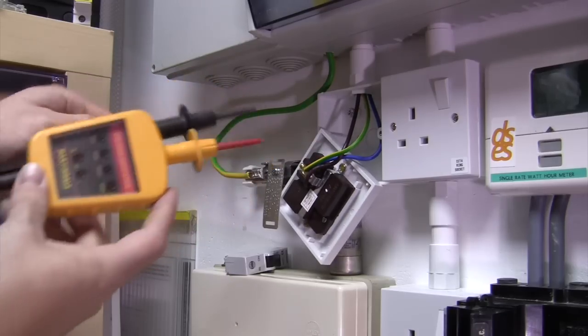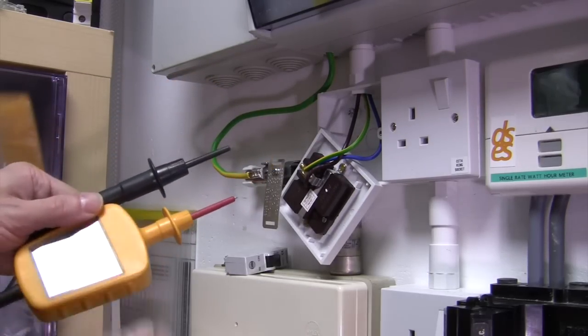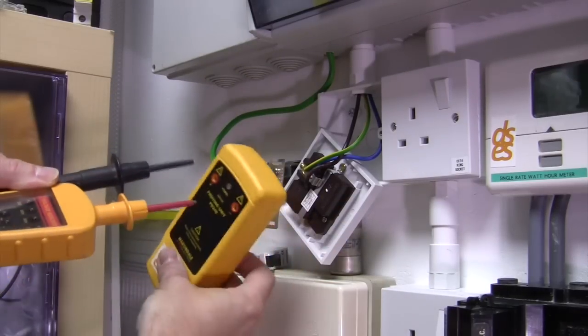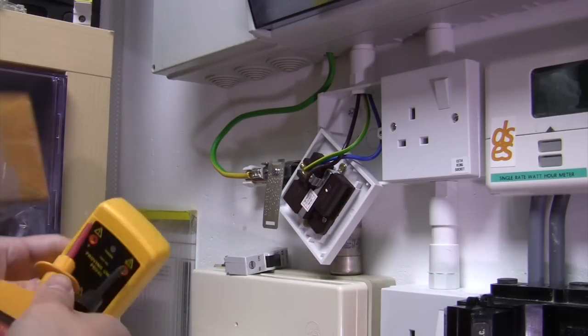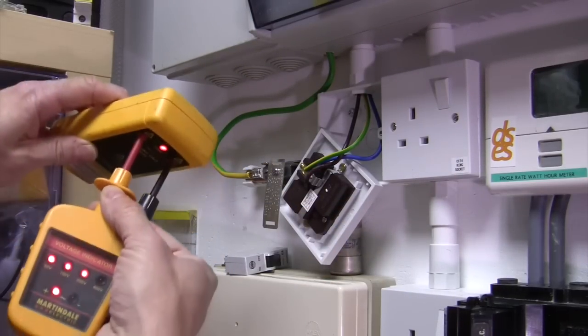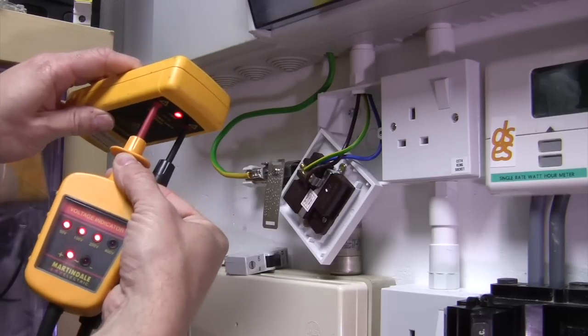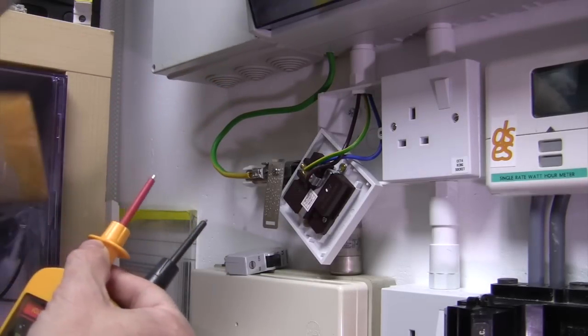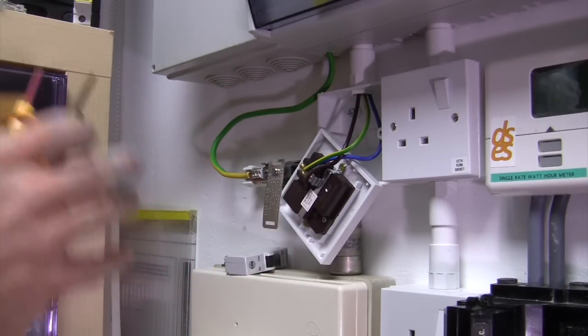And sure enough, I'm getting no indication on any of my indicators there, but I've got to, of course, make sure that my voltage indicator is still operating, so I check it against a proven unit or a known good supply to make sure that it does indeed light up. So I can be reasonably confident here that all combinations of conductors are dead and that this circuit is safe to work on.